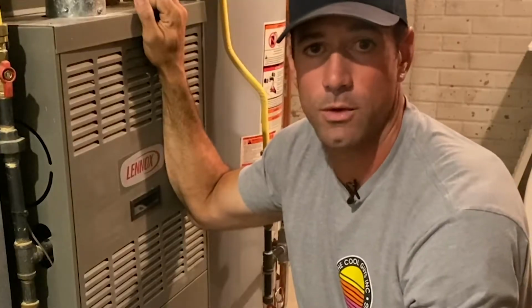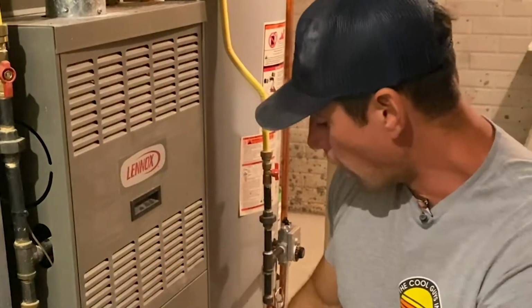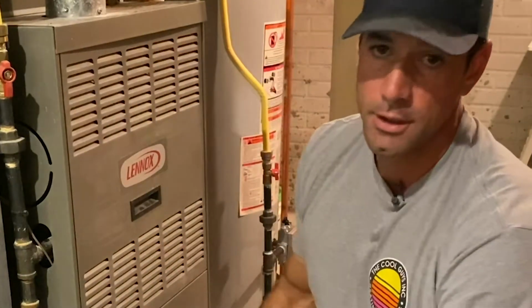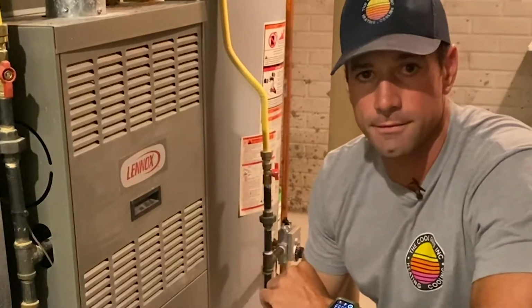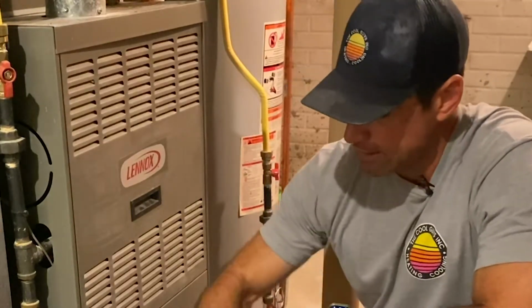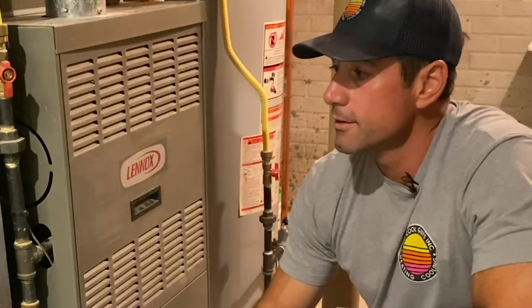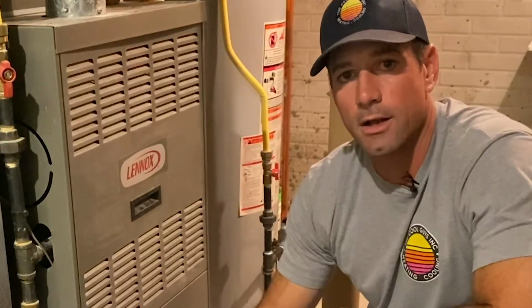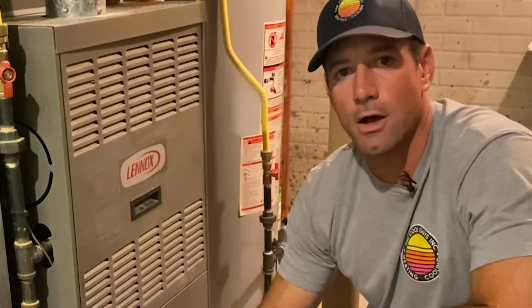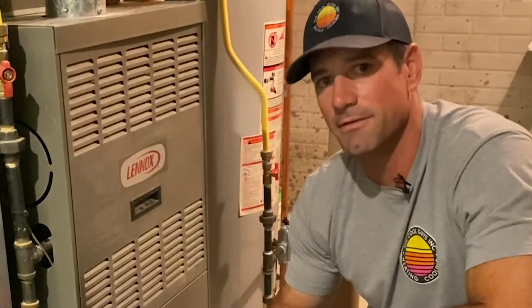If your AC is not working and the filter was extremely dirty and you see water around your furnace, you're going to want to shut the furnace off, just keep the AC off, take the filter out, let it thaw for like a good 6 hours, and then when you go back to check it and turn it back on, first just turn the fan on the thermostat to make sure that the fan is blowing.